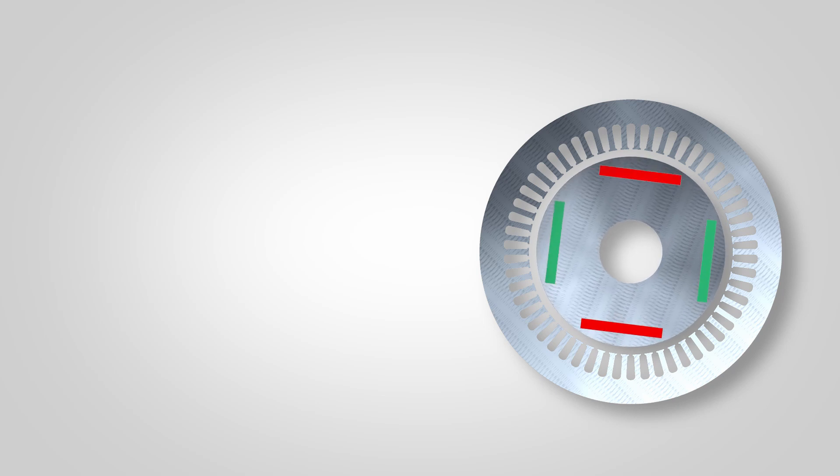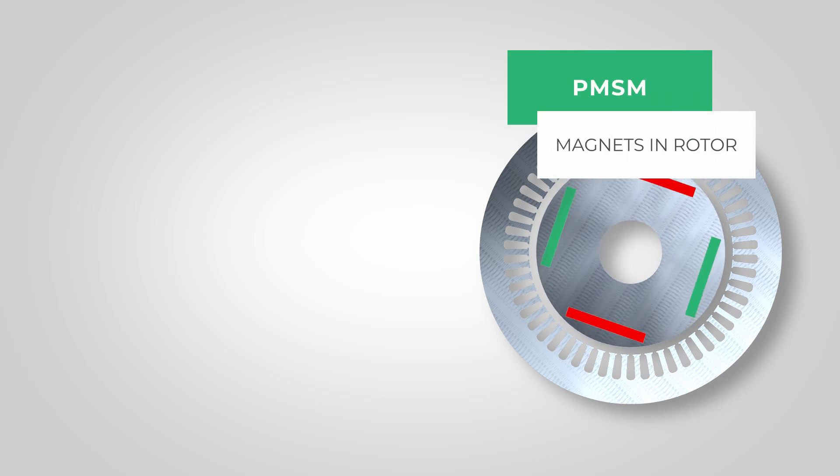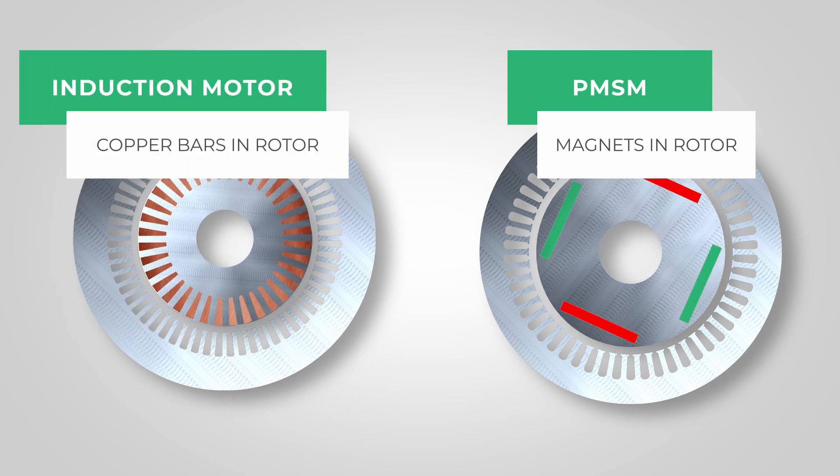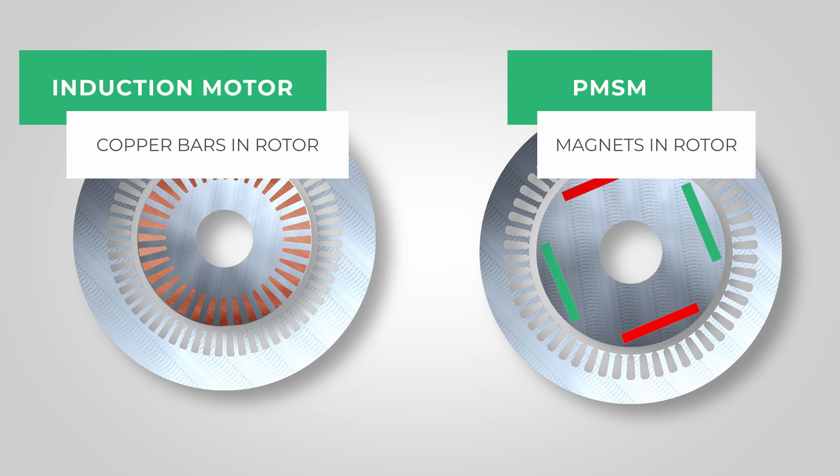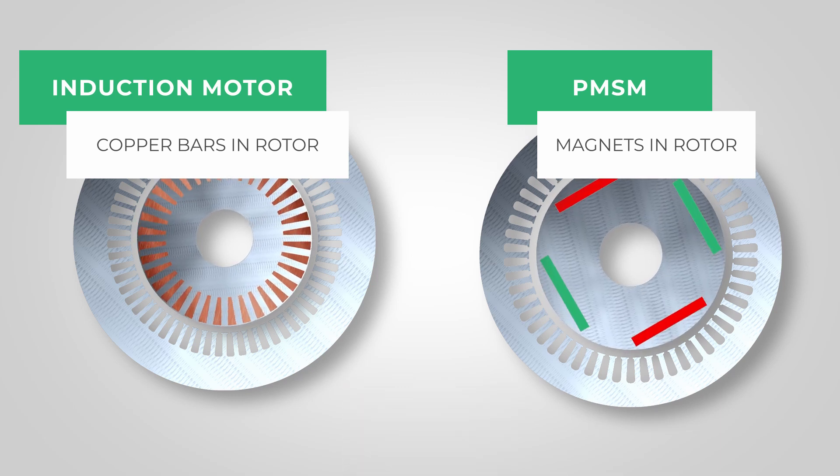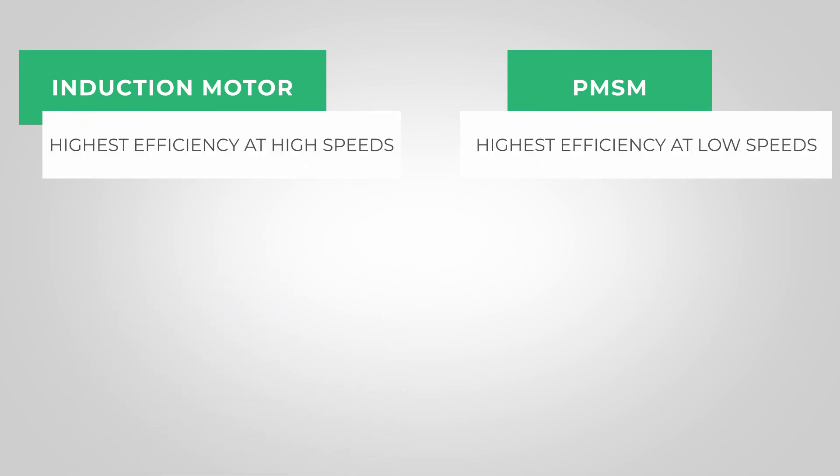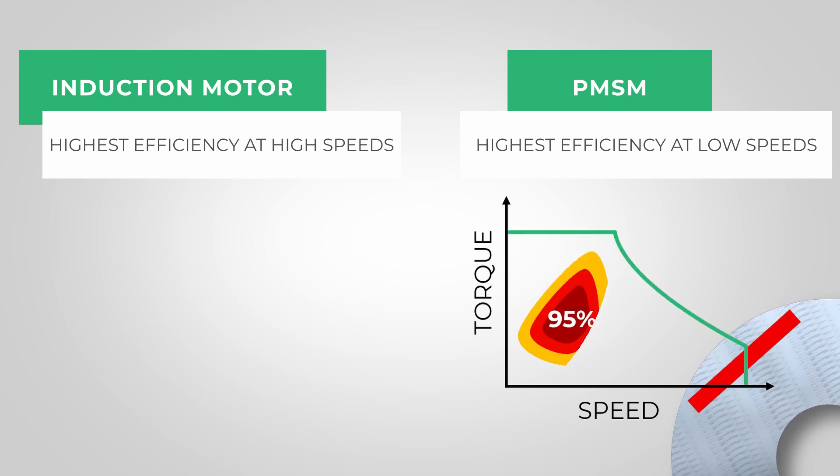A PMSM has permanent magnets in the rotor which follow the rotating magnetic field of the stator. Because induction motors have copper bars in the rotor instead of permanent magnets, an additional current is required in the stator to generate a magnetic field in or from the rotor. This results in the lower efficiency of induction motors in the lower speed range than synchronous motors with permanent magnets.